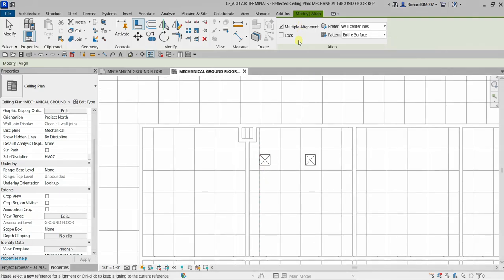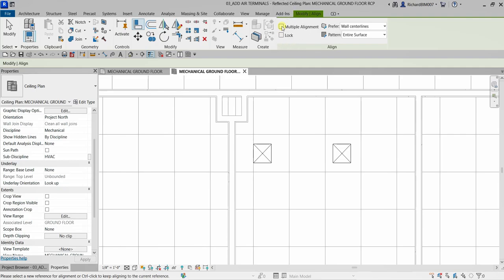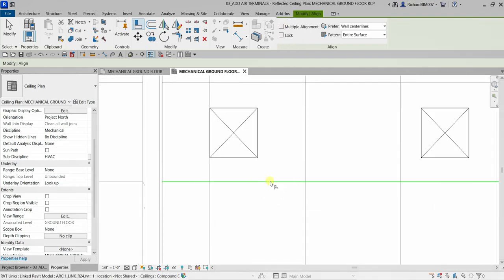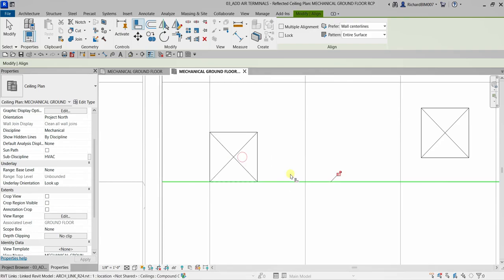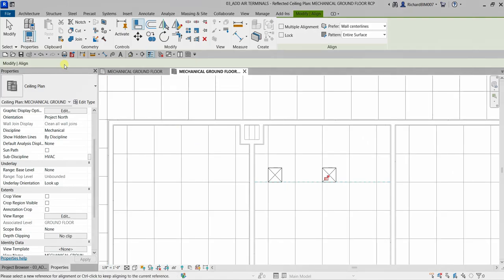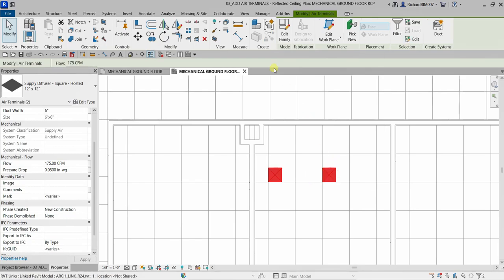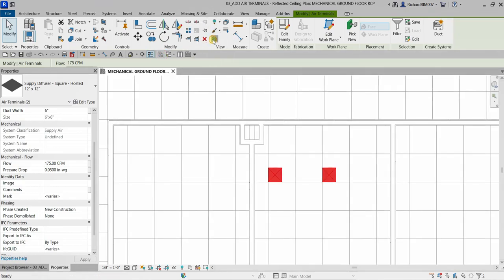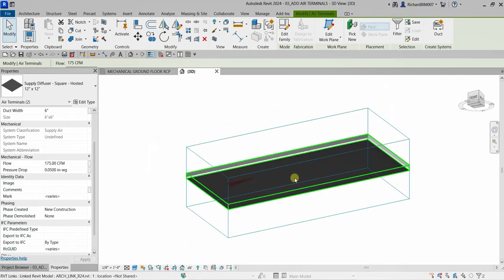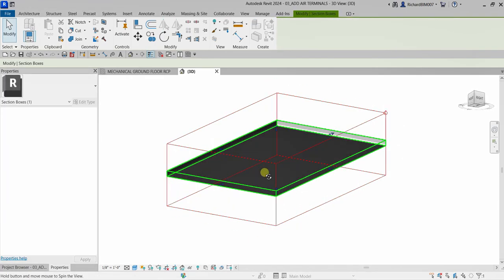The reason for selection difficulty was that 'Multiple Alignment' was checked, so I'll uncheck that. Now I select this line, click it, then click the target line. I'll align the other terminal too - select that side and align it. Then I select both air terminals holding Ctrl, and use the Selection Box to view them in 3D. There are our air terminals hosted to the ceiling.